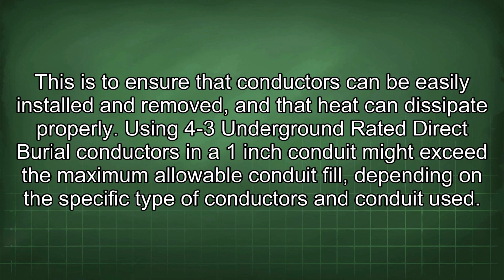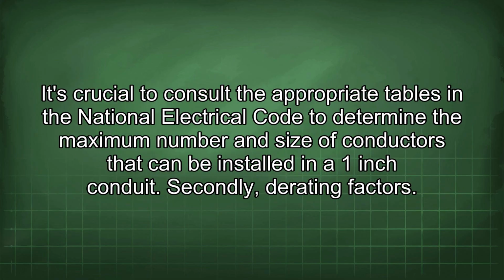This is to ensure that conductors can be easily installed and removed, and that heat can dissipate properly. Using 4-3 underground rated direct burial conductors in a 1-inch conduit might exceed the maximum allowable conduit fill, depending on the specific type of conductors and conduit used. It's crucial to consult the appropriate tables in the National Electrical Code to determine the maximum number and size of conductors that can be installed in a 1-inch conduit.